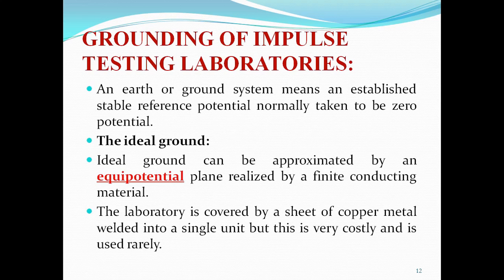Grounding of impulse testing laboratories. Grounding is very important in the high voltage laboratory. When you visit the laboratory, you will find a big difference between an ordinary laboratory and a high voltage laboratory. An earth or ground system means an established stable reference potential, normally taken to be zero potential. The ideal ground can be approximated by an equipotential plane realized by a finite conducting material. The laboratory is covered by a sheet of copper metal welded into a single unit, but this is very costly and is used rarely. It means a metal sheet is there in the high voltage laboratory and all the equipment is put on the metallic sheet.